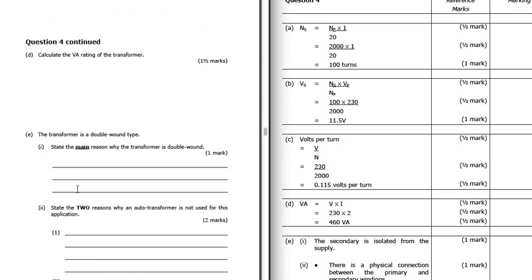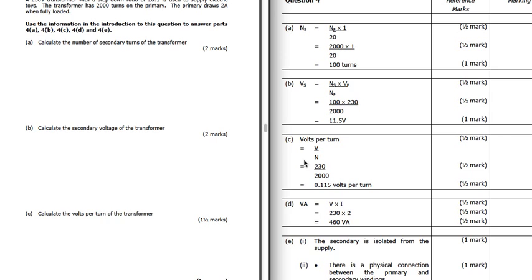The volts per turn of the transformer, we could do that with the primary or the secondary. They've done it with the primary, and it's probably the right decision, because they're the values they've given you. So if you got this wrong and you did the volts per turn with the others, then you'd get that wrong. So use the ones they've given you. 230 divided by 2000. So you've got 230 volts across 2000 turns. How many volts on one turn? It's going to be 0.115 volts per turn.